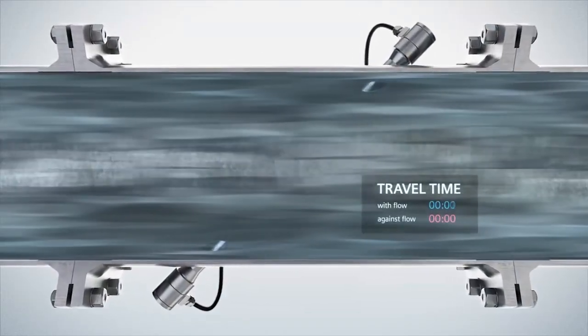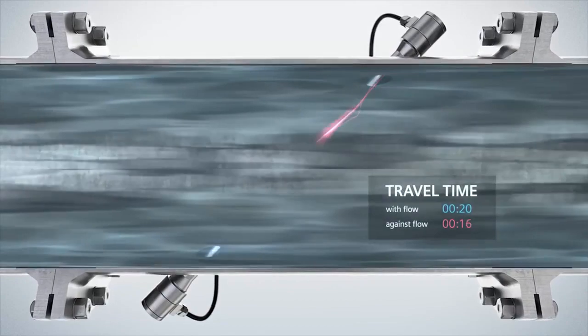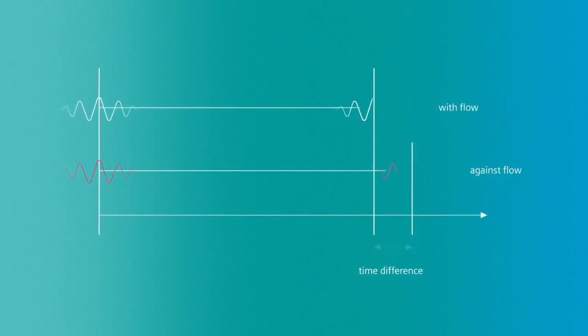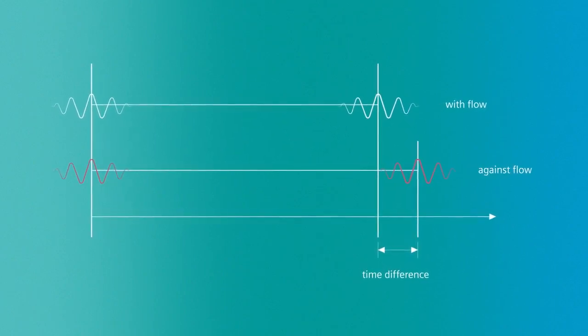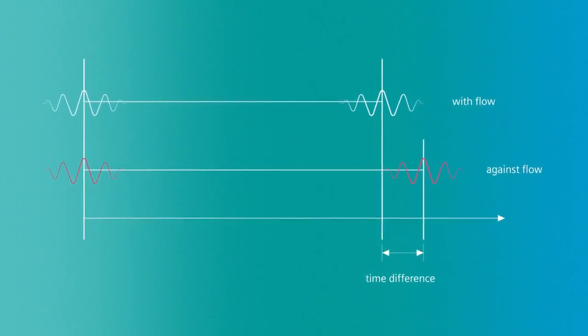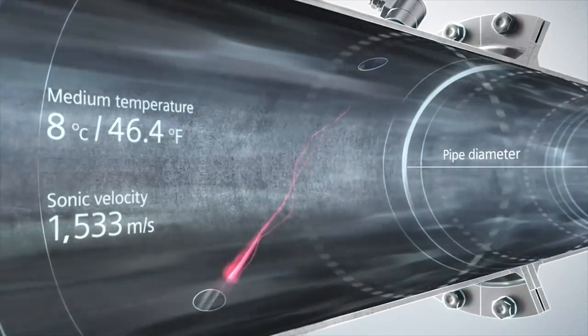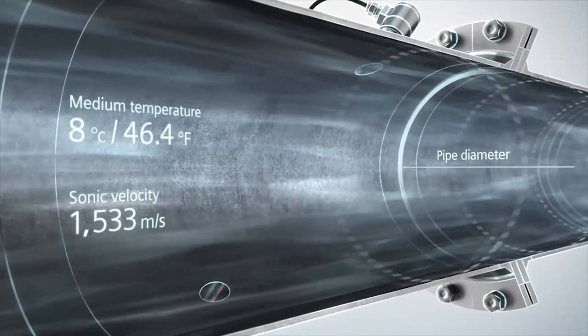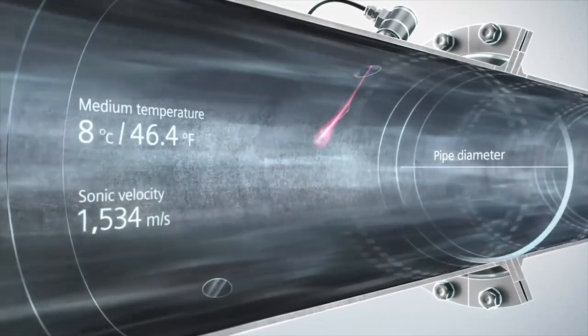When moving in the same direction as the flow, waves travel faster than waves traveling against the direction of the flow. The higher the flow velocity of the medium, the greater the difference between the two transit times. Combined with the known area inside the pipe and the measured sonic velocity and temperature of the media, it is possible to accurately measure the volume.